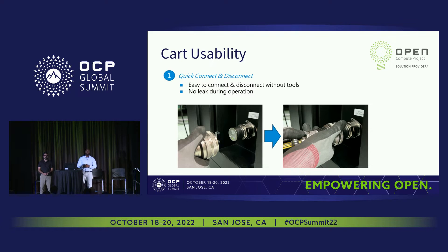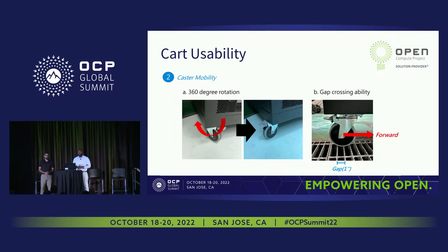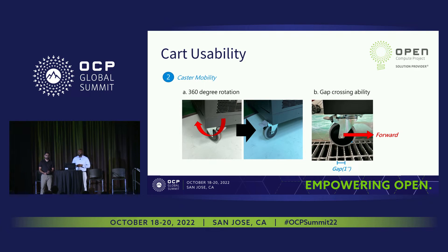In terms of usability, we wanted to make sure the cart was as easy to maneuver and use in the data center for technicians, since it serves such a critical function for servicing liquid cooling. Every system has quick connect and disconnects, which prevents leakage when connecting a hose and makes it very easy for techs to connect the hoses. Regarding mobility, two of the casters are locked and fixed in place, and two have a full 360-degree rotation, allowing for easier turning through data center halls, especially for tight 90-degree turns. The cart was also designed to overcome at least a one-inch gap so it wouldn't get stuck during movement.